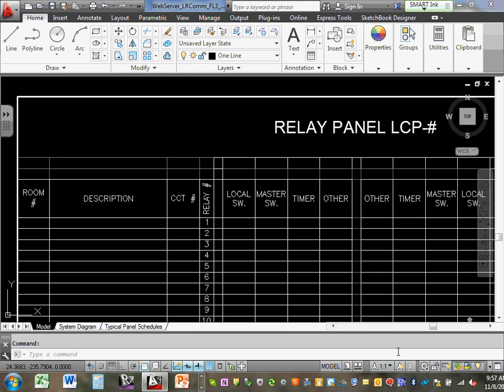You can circuit multiple rooms on one circuit, but when you switch them, you switch them on different switches. So that's what Keith is saying. You have three or four rooms, like in an office, on one circuit, but you switch them from different occupancy sensors and different switches. Every time you switch, you need a relay on an occupancy sensor or on a low voltage switch, for the most part. Good point. And I keep talking about the relay, that molded case device.